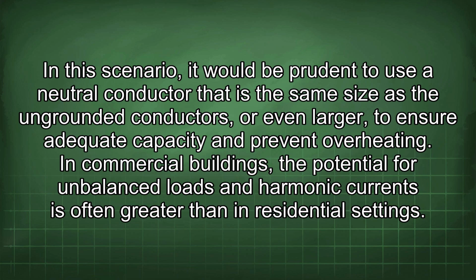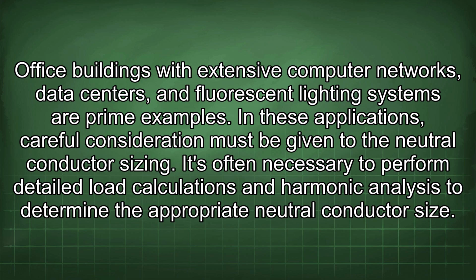In commercial buildings, the potential for unbalanced loads and harmonic currents is often greater than in residential settings. Office buildings with extensive computer networks, data centers, and fluorescent lighting systems are prime examples. In these applications, careful consideration must be given to the neutral conductor sizing. It's often necessary to perform detailed load calculations and harmonic analysis to determine the appropriate neutral conductor size.